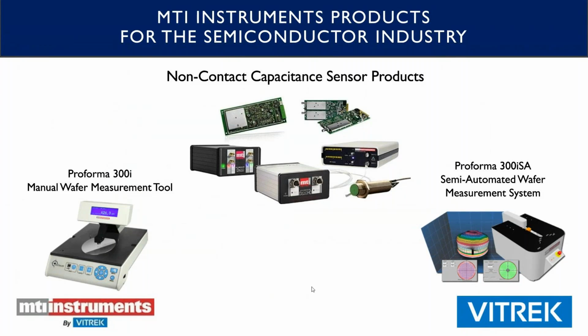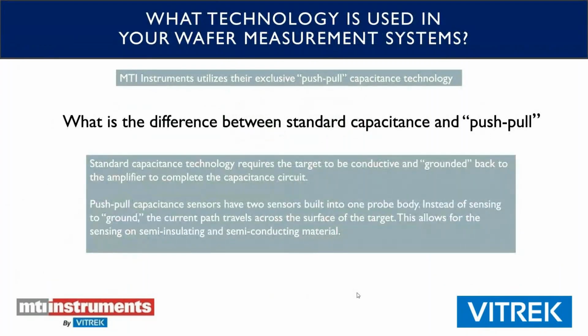Our 300i is a manual gauge. We use capacitance technology. If you're familiar with capacitance technology, the standard technology requires the sensor to sense to a conductive, grounded target to complete the circuit for the measurement. What we employ is an exclusive push-pull capacitance technology for our systems, which does not require a grounded target, which is excellent for both semiconducting and semi-insulating materials. So you don't need a grounded target or anything like that.